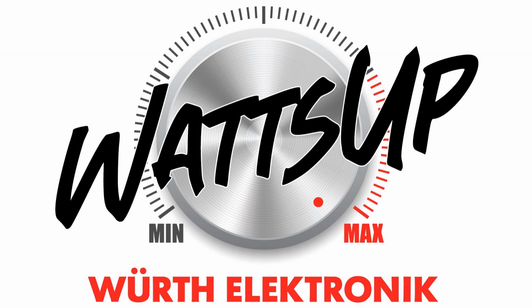I'm opening another tab, and I want to measure the differential mode with the quasi-peak detector. And then I want to measure the common mode with the quasi-peak detector. So what have I done here? Here I've frozen 2 traces of what the DUT is emitting, and I opened 2 traces which are measuring. So right now, if I change the filter and put the big filter, I will see its action on both modes, and then we will compare in real time.